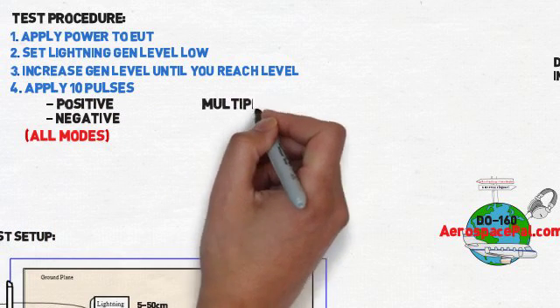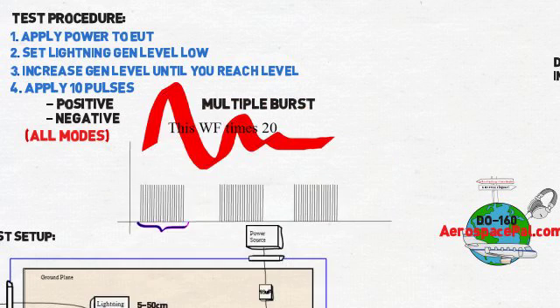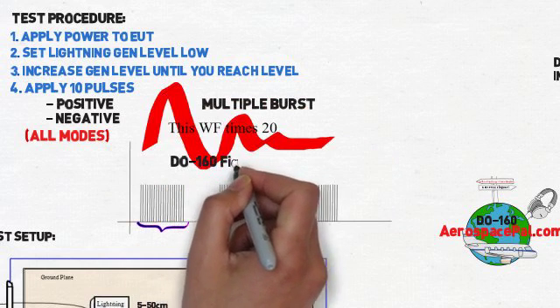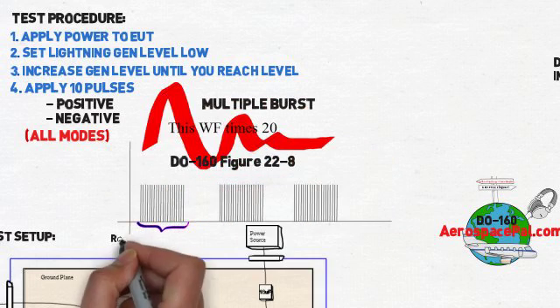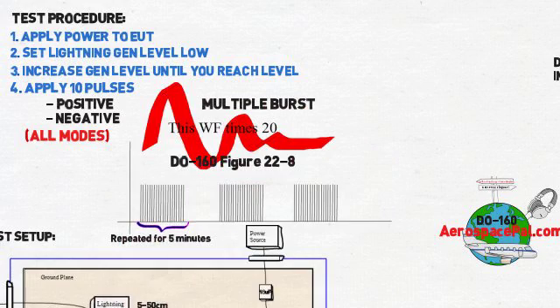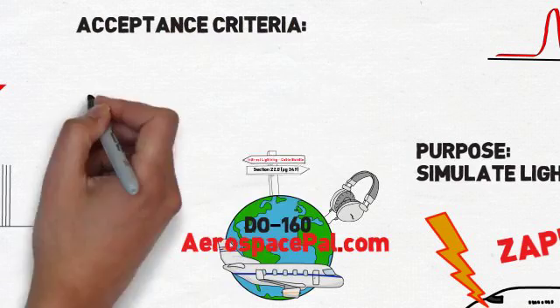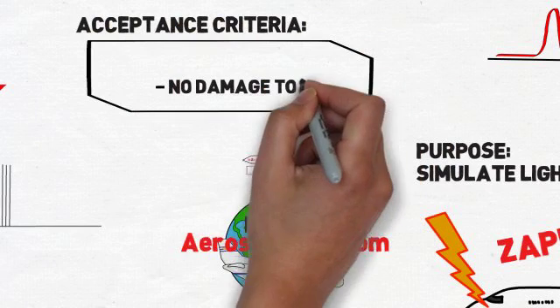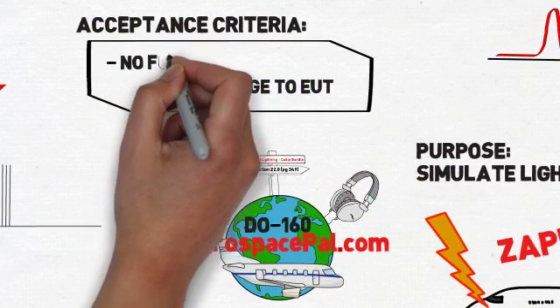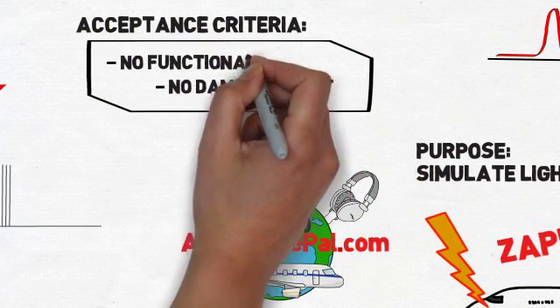Now, multiple bursts is a little bit different. You're going to apply the burst application specified by the figure below every 3 seconds, lasting continuously for 5 minutes. Unlike pin injection, this test evaluates the functional upset as well as the damage tolerance. Monitor your EUT during this test and ensure that you pass.